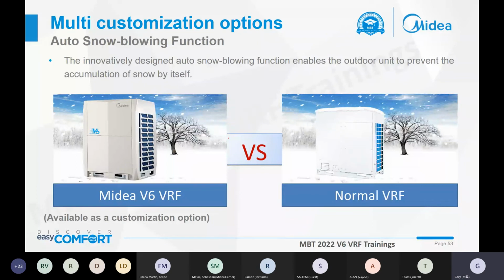Another customization option is the auto snow blowing function. I think this function may be used in Latin America. When there are snow days, the snow will accumulate on the top side, which affects our unit's heat exchange, so we should remove the snow. There is an outdoor snow blowing function. When it detects that the airflow pressure at the air outlet is too big, this function will activate to remove the snow.